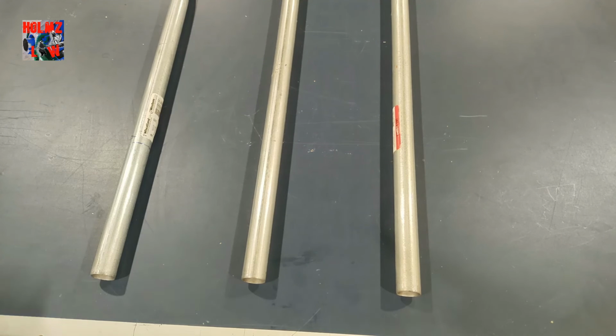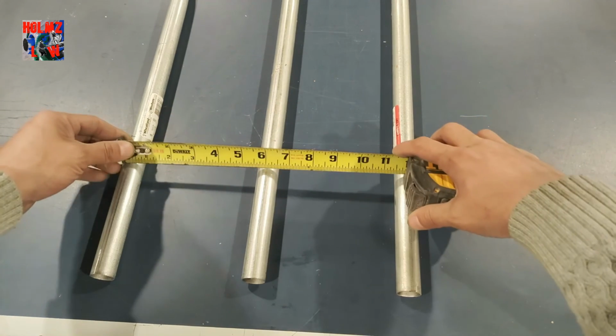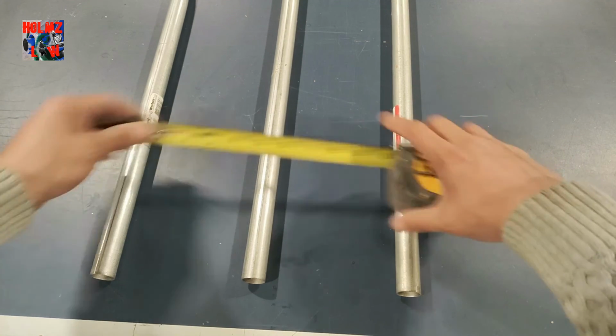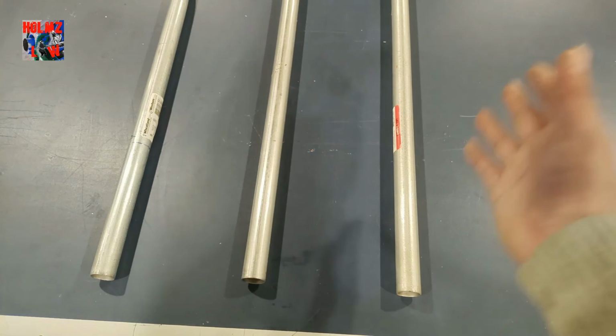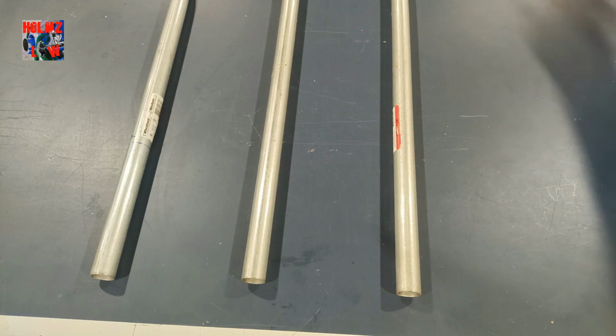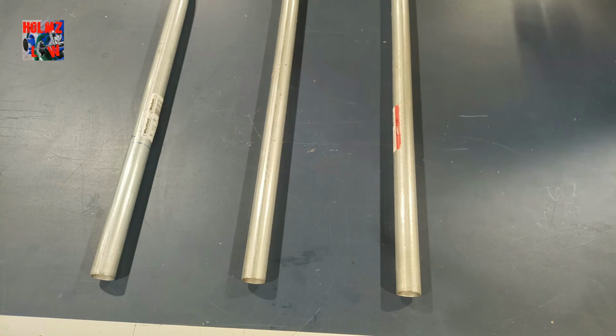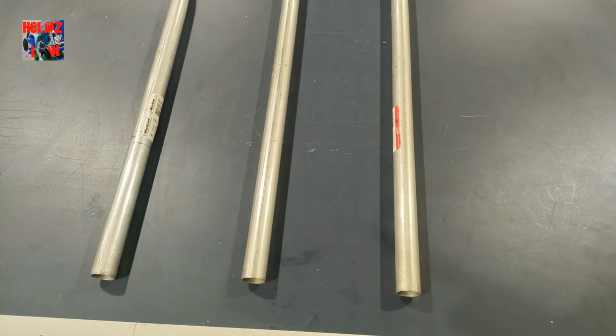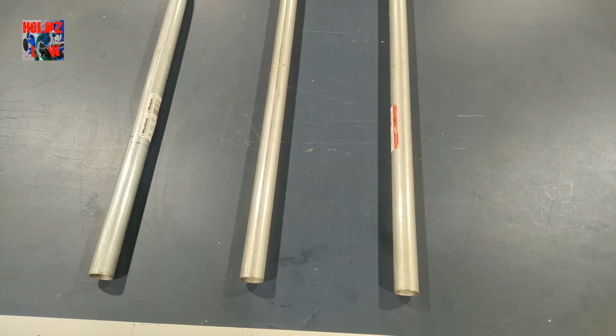And the spacing, as you know, on the slides is going to be 6 inches apart. So basically just about this much here. But when it changes planes, it's supposed to be very close to 6 inches apart as well, and they're not supposed to be touching. Give me a little bit and I will come right back.